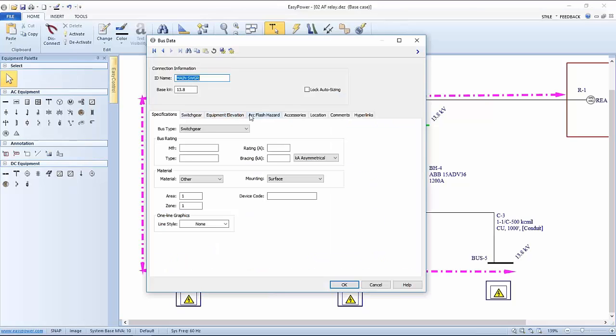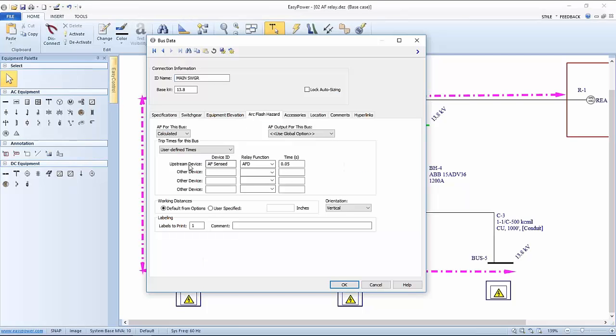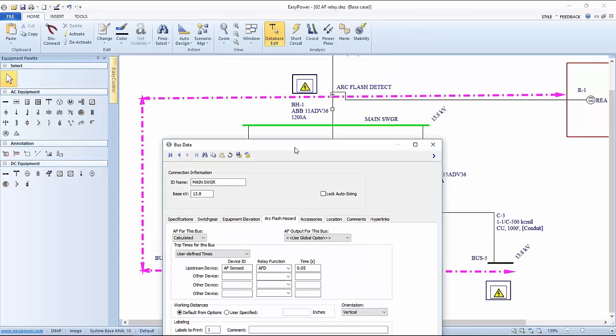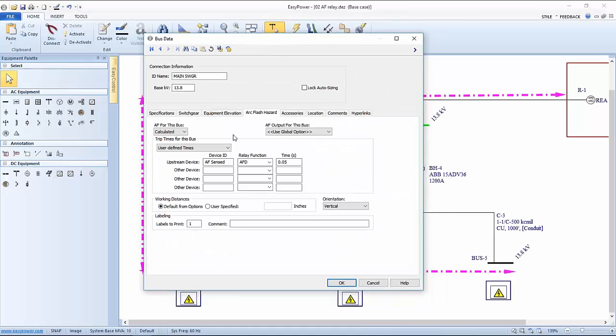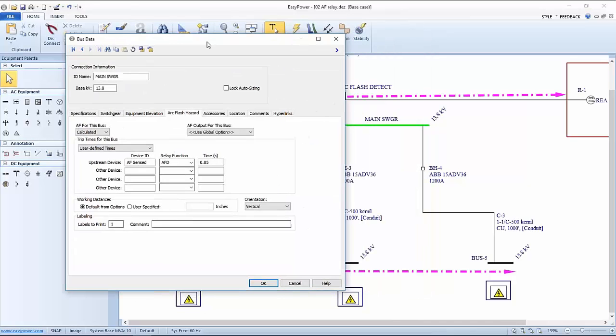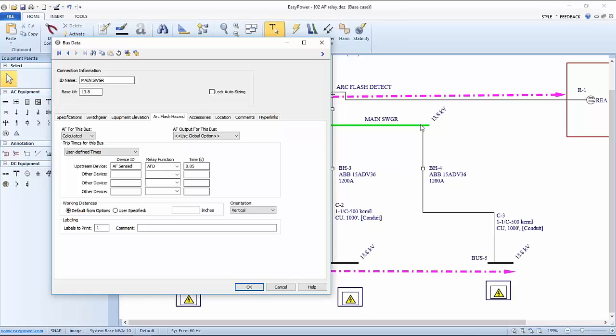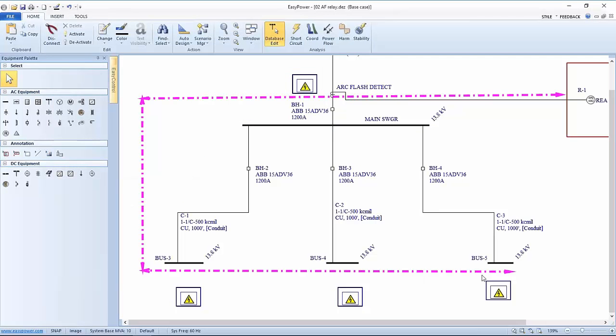As far as time setup or protection setup, I do the same thing as I did in the differential. I'm going to open up my main switch gear. In my Arc Flash Hazard tab. Here, because I don't have any other phase overcurrent devices, I'm just going to use user-defined time. I wanted to convey that the device that's tripping is my Arc Flash Sensed Relay. And the time here is, again, fixed by the delay time of the signal and how many modules I have to daisy chain and or any intentional delay that I'm putting in for whatever other reason. In this case, I'm using, which is kind of high. Let's go ahead and use 15 milliseconds.